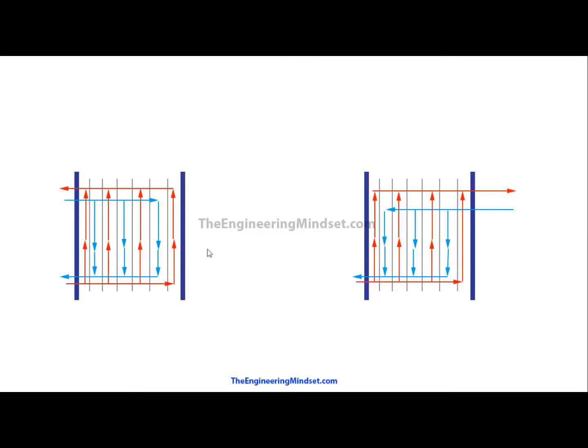This first version is the most common because you don't need to alter the pipework if you extend the plate heat exchanger in the future. With the second version, all the connected pipework has to be removed and remade to fit depending on how far you extend it, so it's not really as practical. That's why the first one is far more common.